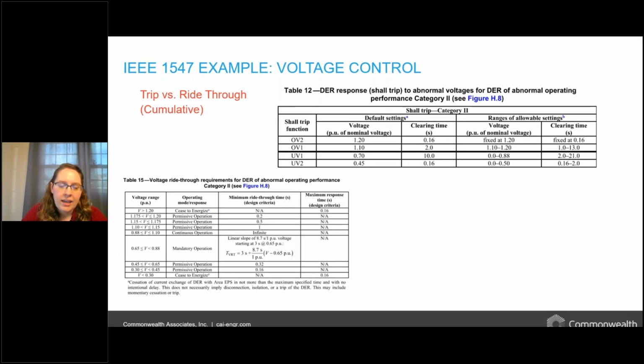So let's take a deeper look at our IEEE 1547 example. And here we're talking about voltage control. On the right, we see a chart from the standard that's talking about trip. That means that we are removing our battery system from the distribution network. On the left, we see a chart that's talking about ride through. That would be cases where we are keeping the batteries connected, even if things don't seem to be staying exactly 100% on the voltage where we normally would expect it to be.